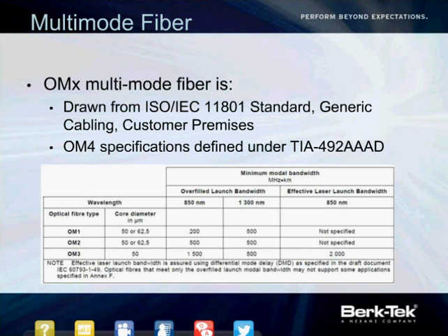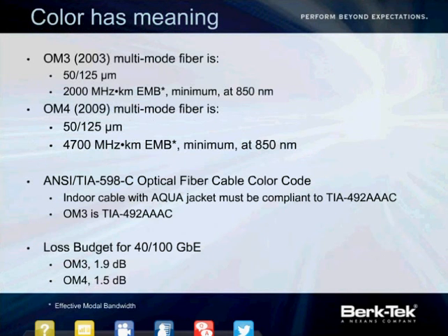OM4, although not listed in the ISO/IEC standard, is listed under TIA-492 — it is OM4 specified in the USA. OM3 means 50 micron and is the minimum level of multimode fiber allowed in IEEE 802.3BA. You see it's 50 micron, 2,000 MHz, and you see what OM4 is. Notice the middle bullet — a lot of people say aqua jacket means laser optimized, but ANSI/TIA-598-C is the fiber and cable color code, which says your fiber jacket colors include aqua.